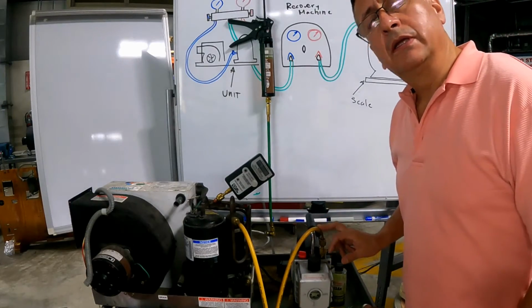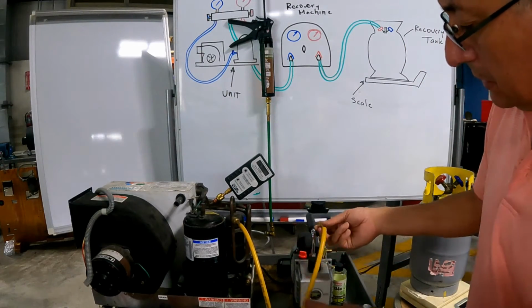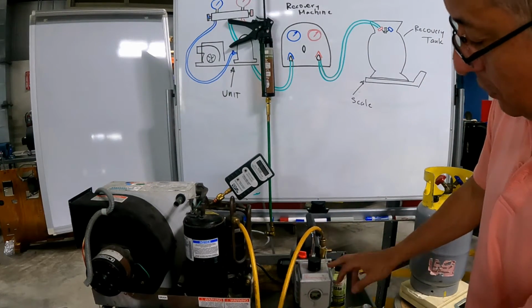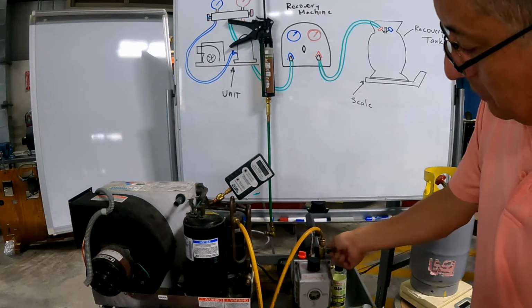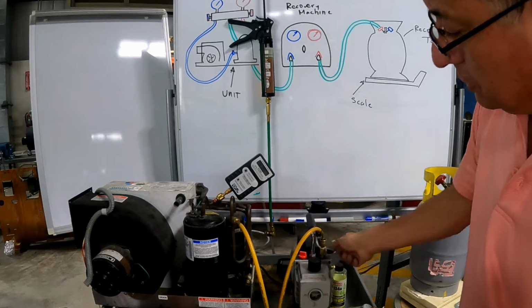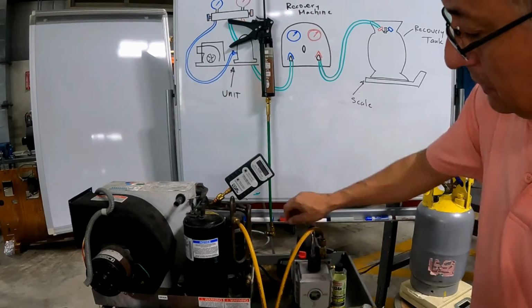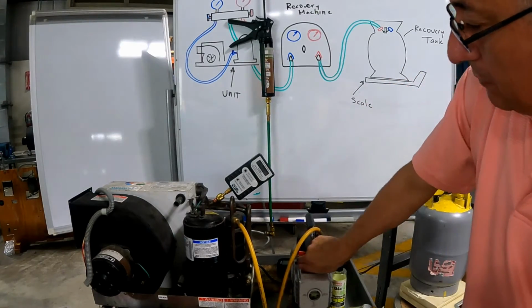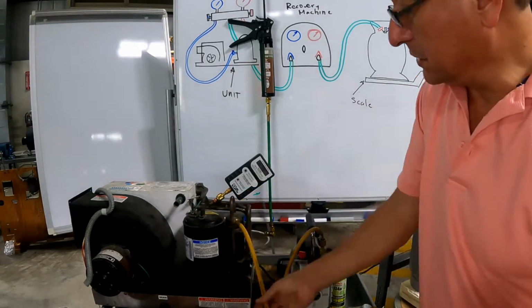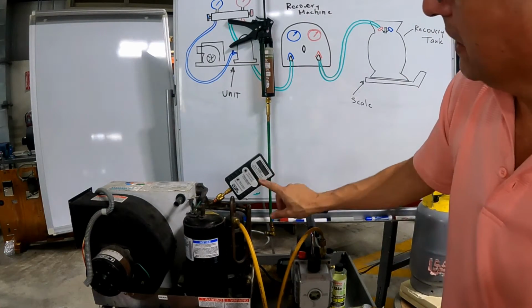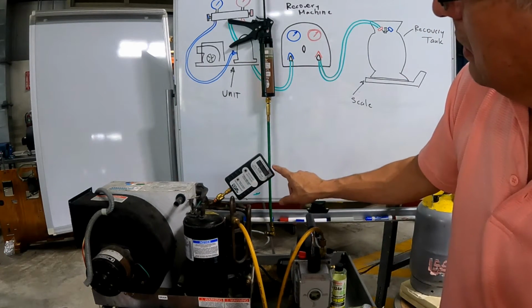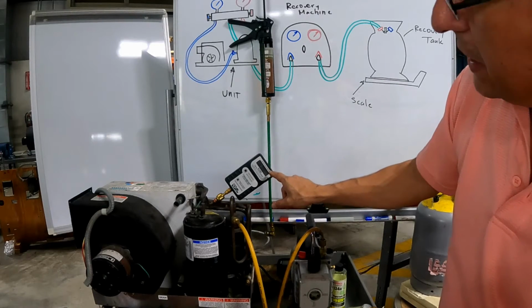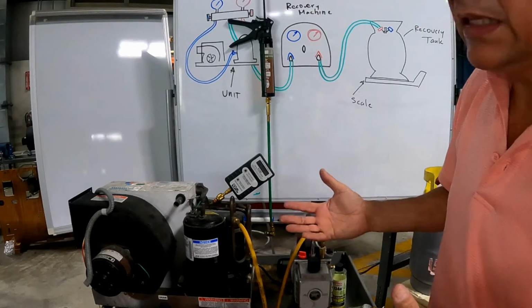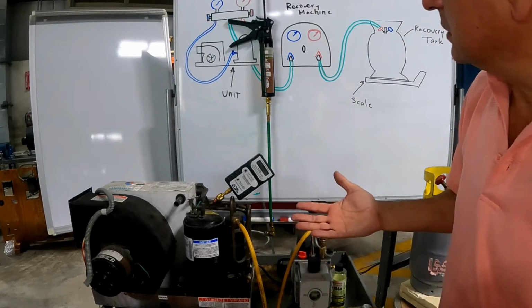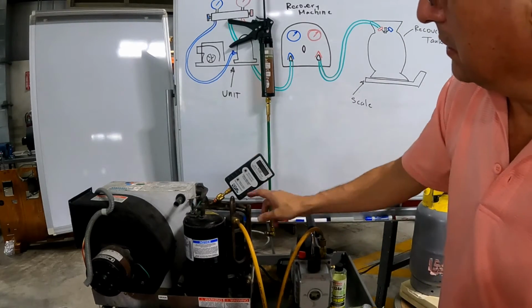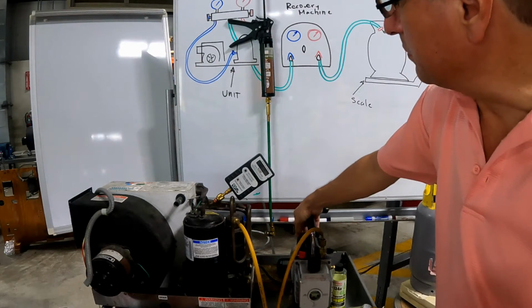Now the system is properly connected. The vacuum pump is properly connected. Both terminals closed. The level of the oil appropriate. The cap of the oil properly closed. The hoses ready, and the vacuum gauge connected. At this moment it's 3100 microns, and the idea is to go down to 500 microns. This is the recommended micron level. We are going to start the process right now.